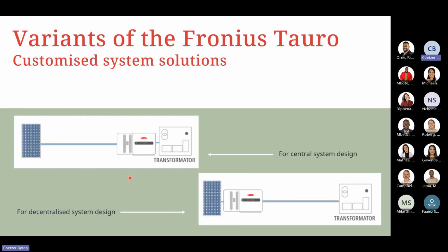Again, I mentioned the different variations of the Fronius Tauro. You have your pre-combined variant for your central system designs, as well as the direct variant for your decentralized system designs. It all depends on the limitations for the site and also the cable losses that you have calculated on site. If we can get away with more loss on the DC side compared to the AC links that we need to pull, we can then use the pre-combined series. This means we can get away with shorter AC runs, which leads to less cable loss. Whereas depending on the design that we have, this is typically what we recommend for the direct variant that you want to use.